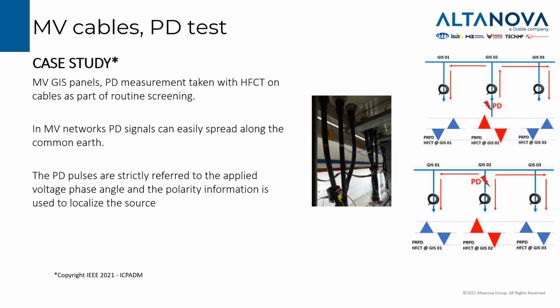I'm reporting a case that was presented at the ICPADM, the IEEE conference in 2021, using TechImp instruments. We're talking about a medium voltage GIS panel, and the measurement we're taking with HFCT on the cable. And this testing campaign was part of a routine screening of the substations. And since we can have quite a spread signal distribution along the common earth, it is quite important to refer the PD to the proper applied voltage, so we can study the phase resolved PD pattern, and we study as well the polarity of the pulse that we measure at each single detection point.